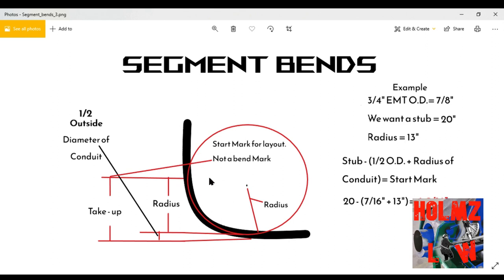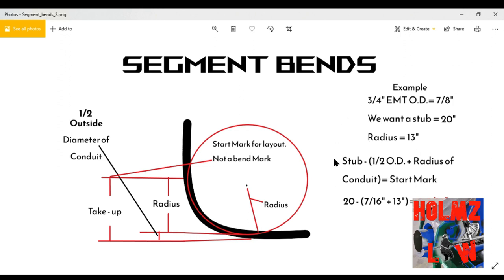You measure six and nine-sixteenths and make that mark — that's where you start your layout from. That start mark is your first mark of the developed length. At no point are these bend marks yet; this is just to start laying out your conduit. It's also important to know the outside diameter of whatever conduit you're bending.